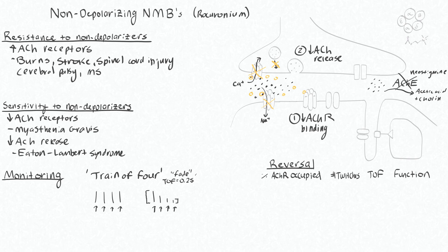If you give even more of your neuromuscular blocker and do four bouts of stimulation, you'll have a single twitch height that starts to decrease, your second twitch is even smaller, and then there will be no response. Here you can't even calculate a train of four ratio; instead you would say you have a train of four count of only two. So your train of four ratio is not applicable, but your train of four count — or number of twitches — is only two.